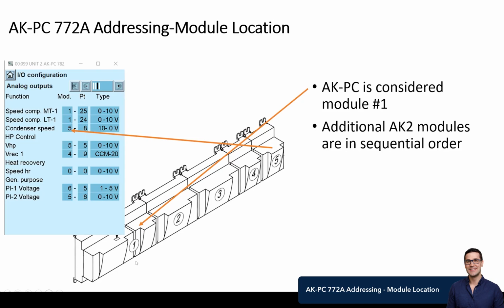So module 1 would be the main 772A itself. And then if we have something like the 208C for the stepper valve outputs, then that would be maybe a second module that we would put into that position. And then just which output or input on that specific board are we wiring to for that function. Okay, so for sure with this option, it will be 1 and 2 because we only need those two for an example. Yep. The 772 and the AKXM 208C.